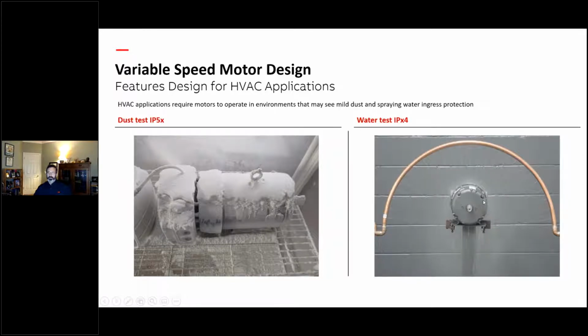And then the water test is, you actually put a white dye inside the motor. It reacts to water and turns a blue color, and you put it in the spray chamber, and it's just like garden hose pressure, so it's not high pressure, but none of the water can get inside the motor. And so that's what gives you, again, for HVAC systems, it's recommended like IP54 as a standard to just protect the product. But it's probably a higher integrity than you're going to see in every application, obviously.